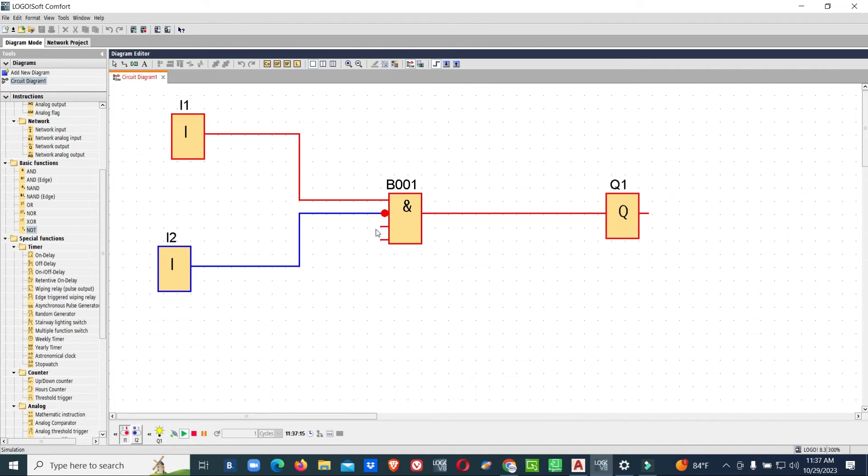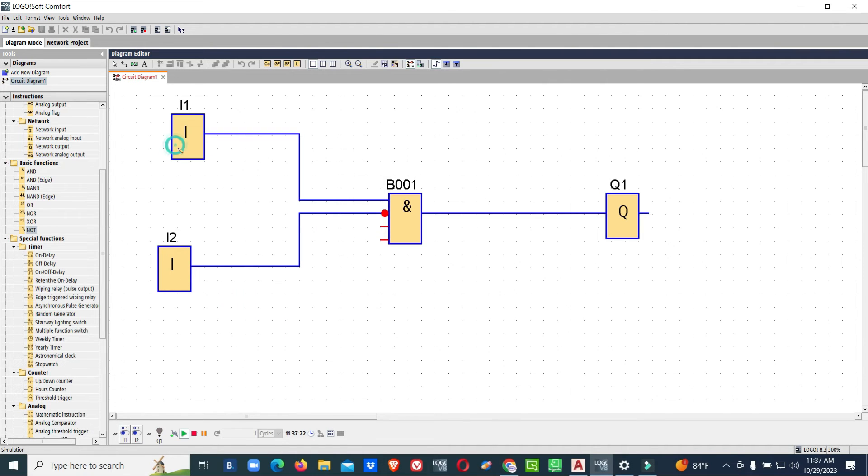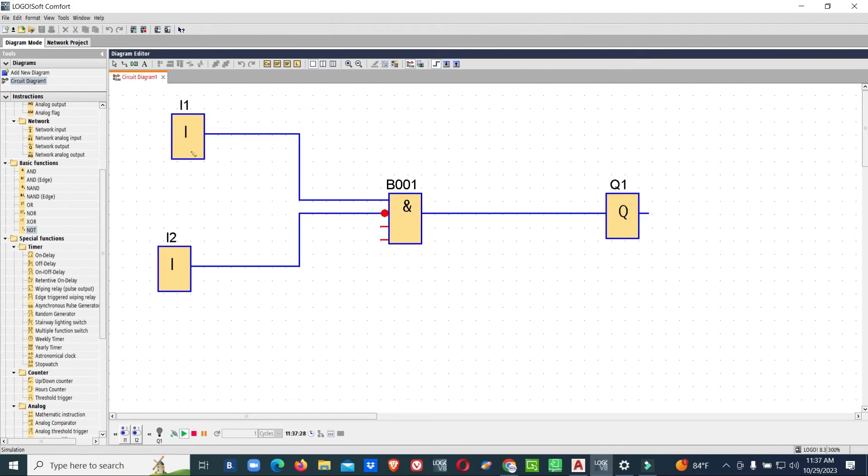Now you can see we have avoided the NOT gate. Now we are using it as NC contact of the input 2. So now the interlock is provided. When both inputs are available we will not get output. Only when the first input only is available, we will get output.